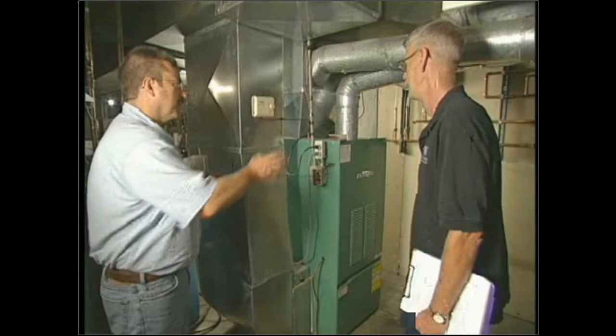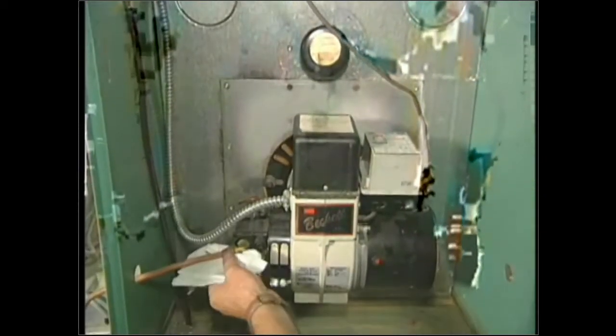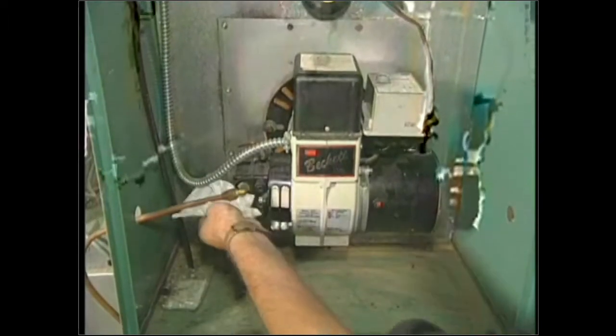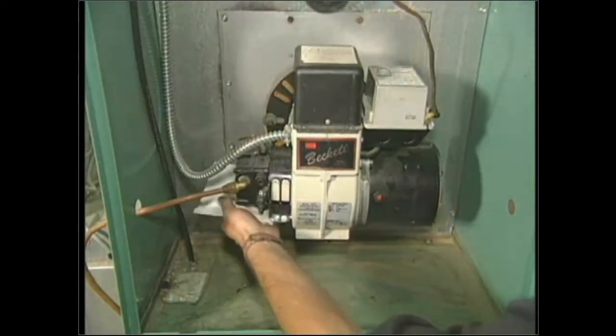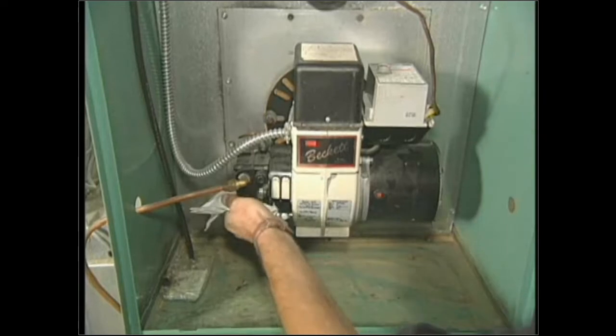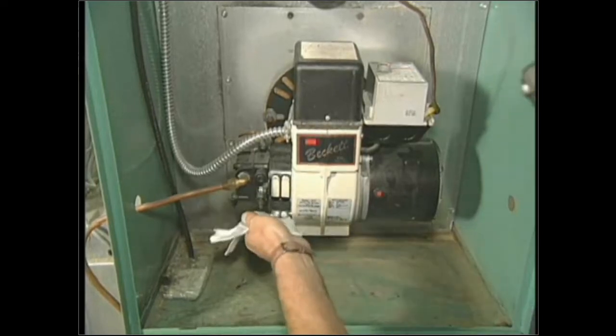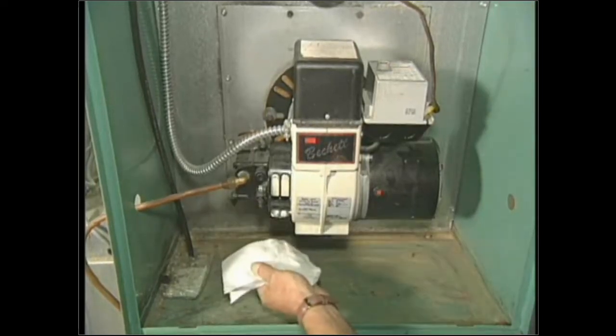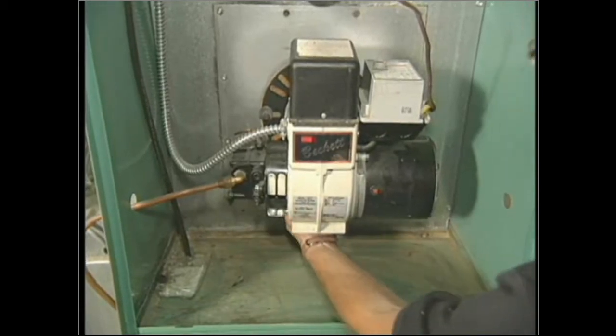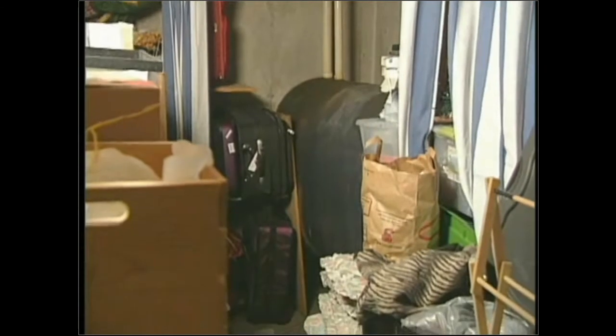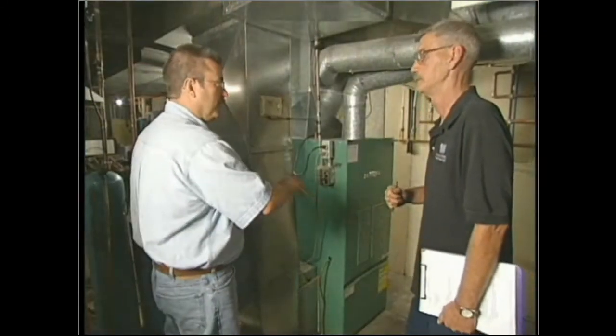Okay, so is it important to do this inspection with the furnace sitting idle, not running? Yes, because this pump pulls a negative pressure on the fuel line and pulls the fuel to the furnace. When it's sitting idle is when you have your oil leaks. Otherwise, when it's pulling, natural pressure will pull inside the cracks. And from the auditor standpoint, don't be surprised if it's buried in a corner, if it's difficult to get to. It seems to me it's imperative that you do these inspections. Okay, so we do a thorough inspection of the fuel tank, the fuel lines, all the unions.